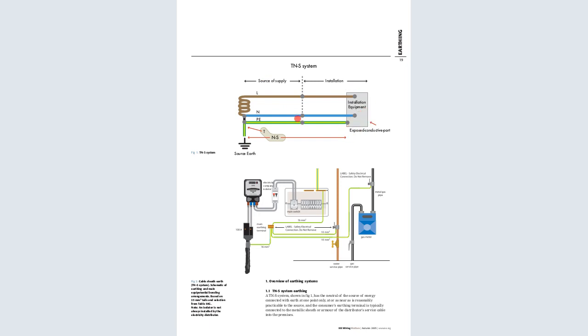This is the source of the earth. You can see that this is the TNS system. So this is the equipment itself that is supposed to be earthed, and this is the live wire, and this is the neutral wire. When they come here, they join at this point, and then, with T and S, it means that the earth and the neutral are separated. They're separated at that point.